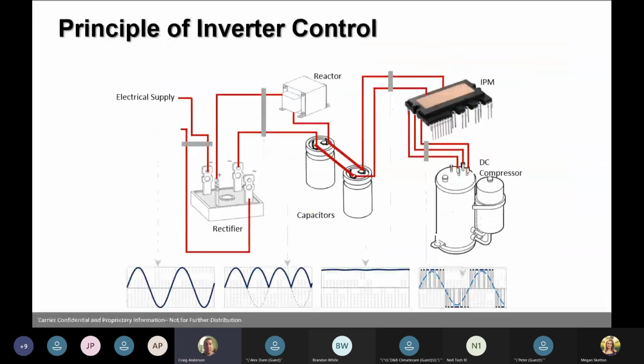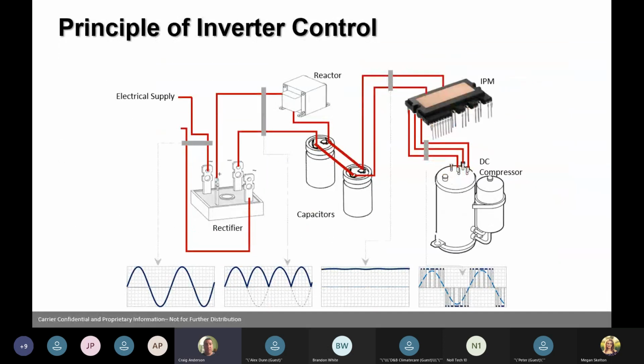So the typical principle is that electrical power comes in and goes through the rectifier, where we clean it a little bit. We go through a reactor, which cleans it a little bit more. Once we're through the reactor, we store that power in the big capacitors in the unit. Then we go to our board, which feeds our compressor and then our fan motors. Just a little idea of how it works: clean the power, send it to the proper controls, and then we can send it to our compressors.